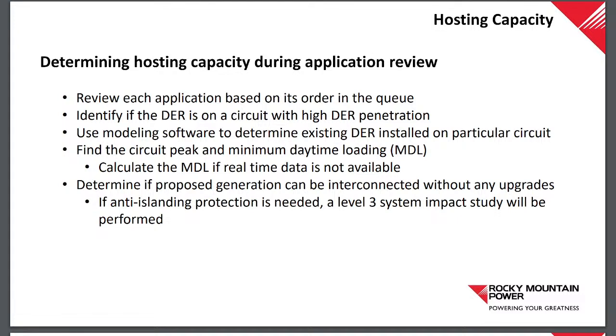If you really want to get into the details, you take 72% of that active generation on that circuit, then add that to what we actually saw to say, okay, there's our minimum load if we take that generation off. Or we'll just say the net, if we have SCADA.